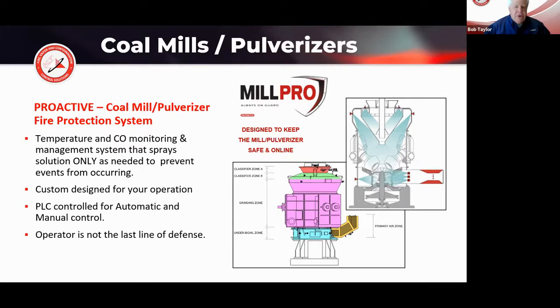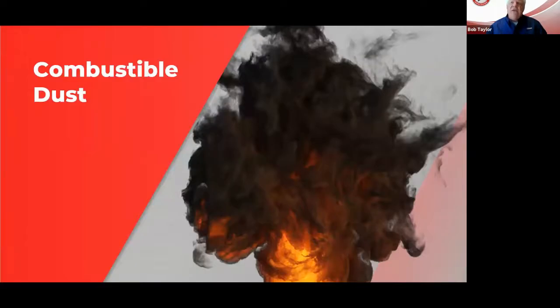Hazard Control Technologies, in partnership and working with others, has developed a very proactive system for coal pulverizers and mills known as MillPro. It monitors for carbon monoxide and temperatures and can very quickly introduce the agent into the system at the minimum amount needed. It's all custom designed, all automatic, so often before an operator can even in a split second pick up that something's changing in there, it's already addressed the change - another one of those elements putting a barrier in for human performance. That's another system that is interactive and under collaboration with F500 encapsulating technologies.